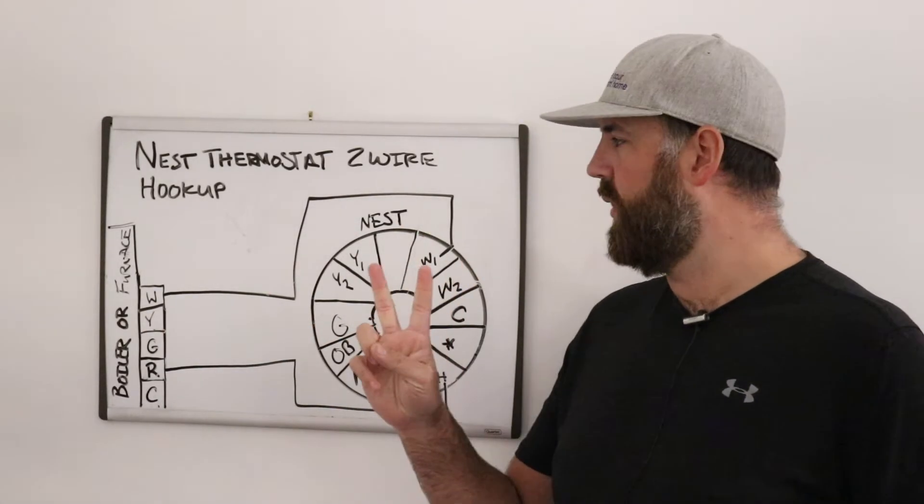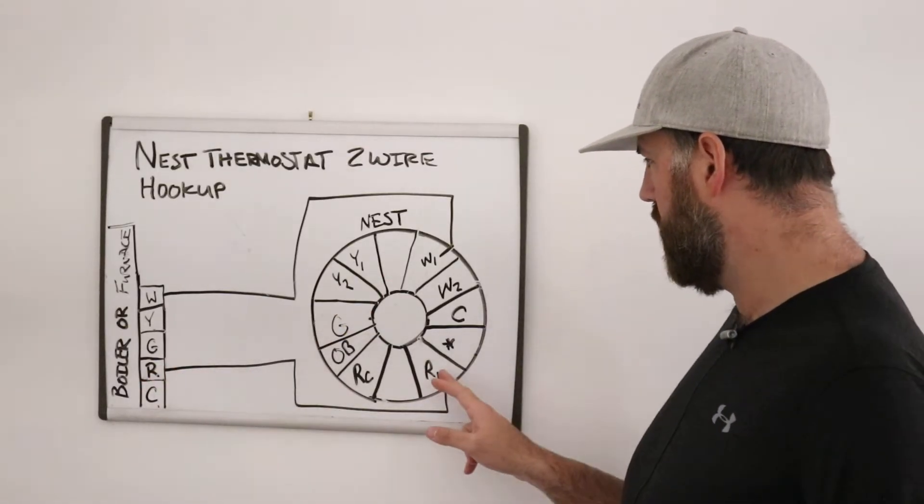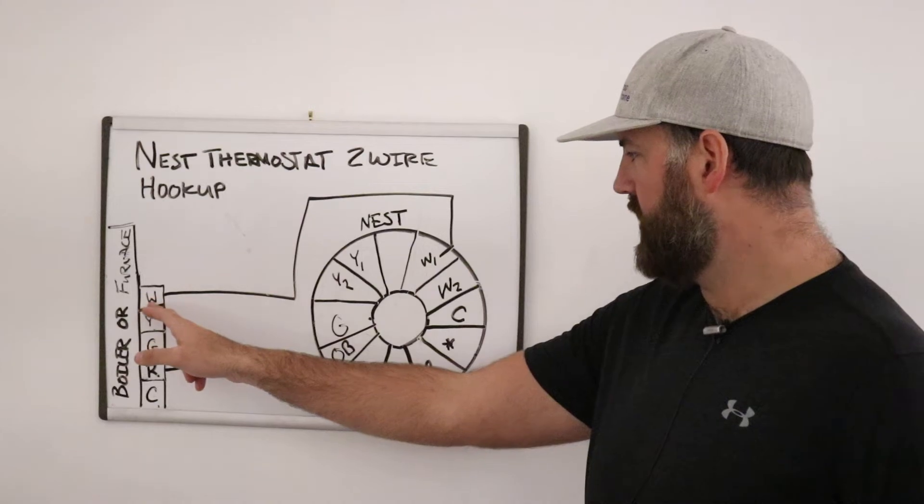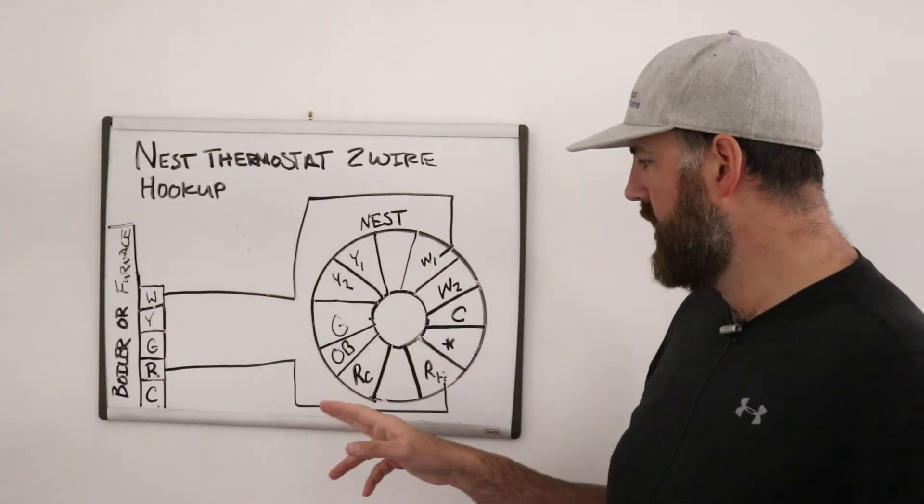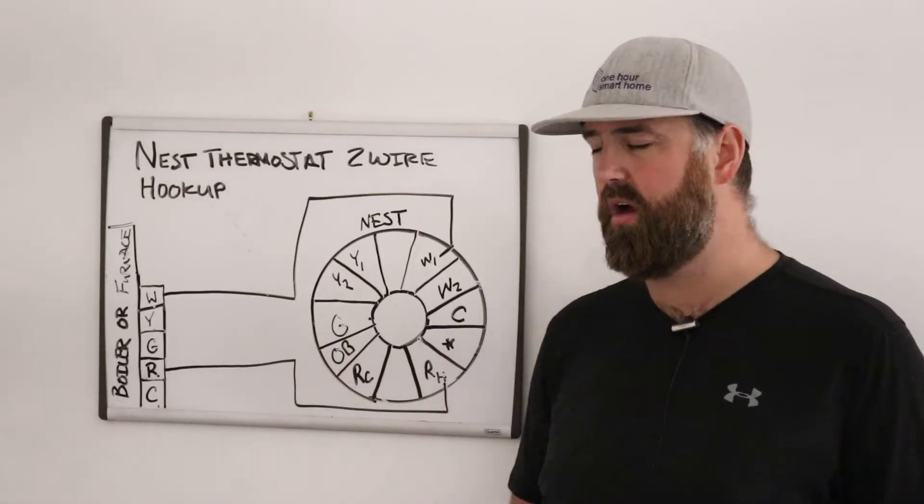And if you've only got two wires, this is the wiring diagram. You'd connect R to RH and W to W1. And typically these wires are going to be red and white. Not always though.